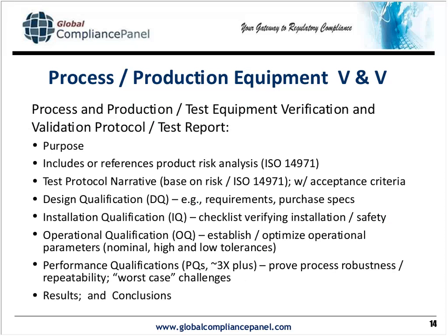Now, obviously, in addition to the product itself, you have your manufacturing process. Now, if you're just developing this on the same production line as other things, you may have some minor changes to parameters, etc., which would have their own verification and or validation, or more than likely you're developing a whole new production line, in which case you've got production equipment to be testing, validating, as well as test equipment and procedures to be tested.